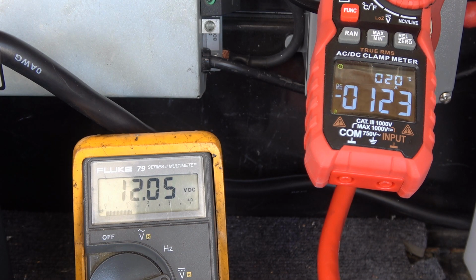Okay, so that's been about 3 minutes now, and it's still running at 123 amps, which I don't think is very good actually, because the cells in there are rated for 100 amps discharge rate, so it doesn't seem like the shutdown is working properly. I'm going to go a little higher. 150 amps. Really, that battery should be going into protection mode, and it's not. We're up around 4 minutes now. Just going to shut her down.